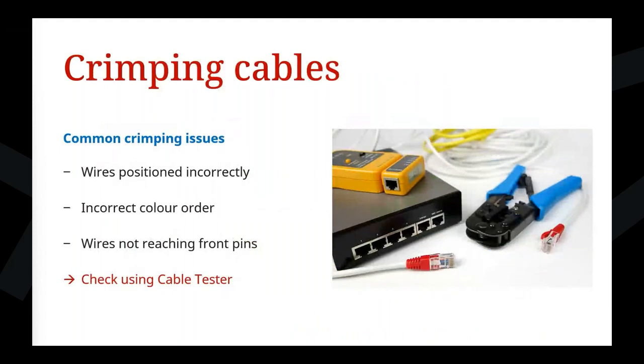When it comes to crimping cables, as I said, we highly recommend using pre-made cables for communication, as it cuts out a lot of potential errors. However, if you are using crimped cables, then these are some of the issues that might happen, so you might want to be aware of them if you're finding the communication's not working. It might be that the wires are not positioned properly before crimping, or the wires are in the incorrect color order before crimping. Another one is wires not reaching those front pins, so the contact doesn't actually pierce properly. If you are making up your own cables, always check them with a cable tester. There are plenty of different ones on the market, and also carry pre-made cables so you can check if it's an issue with the crimped cable.